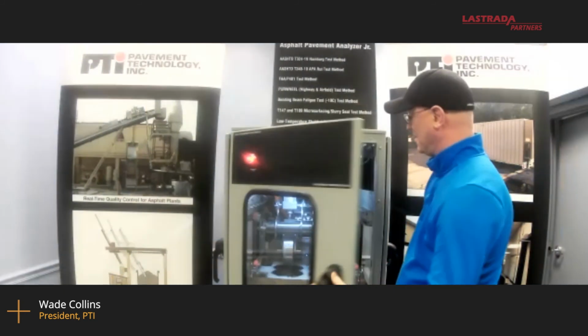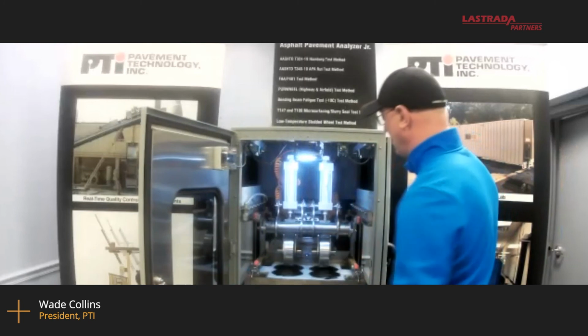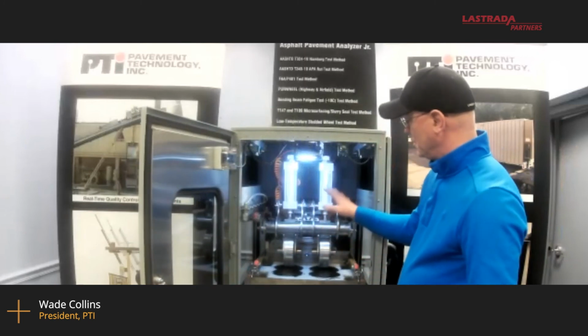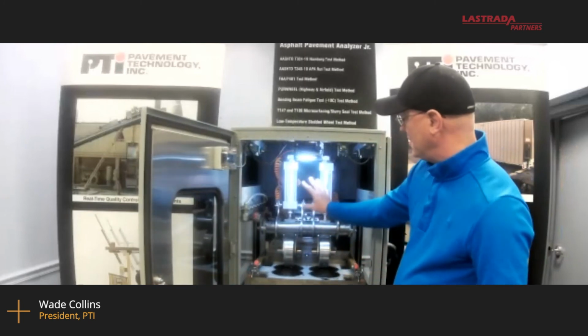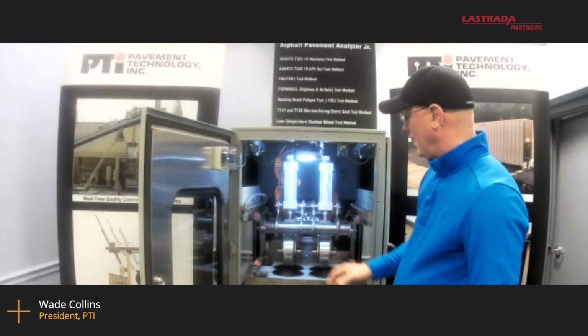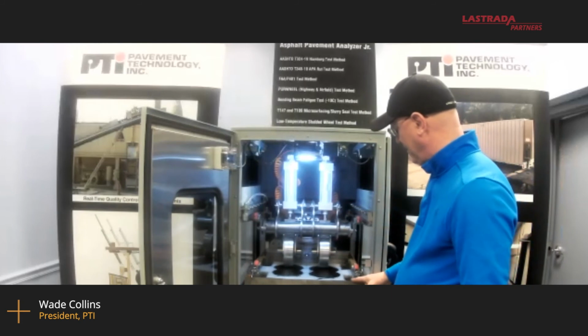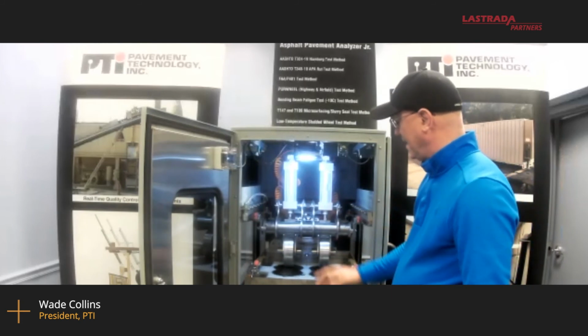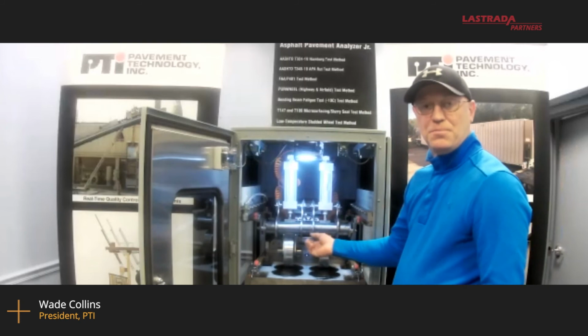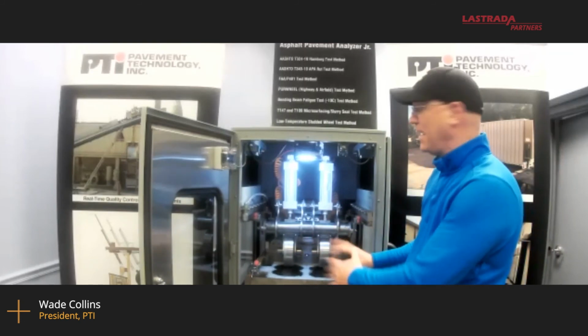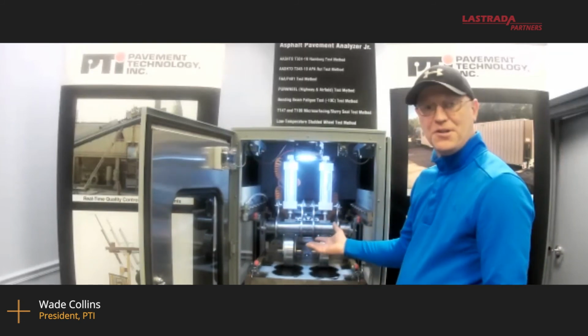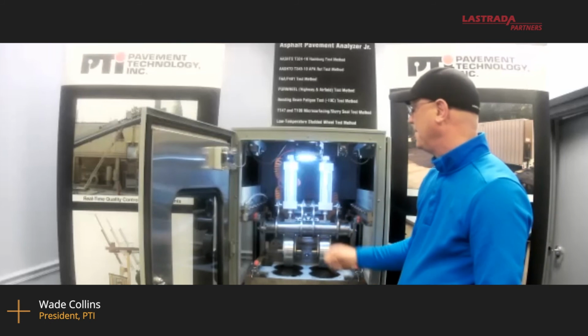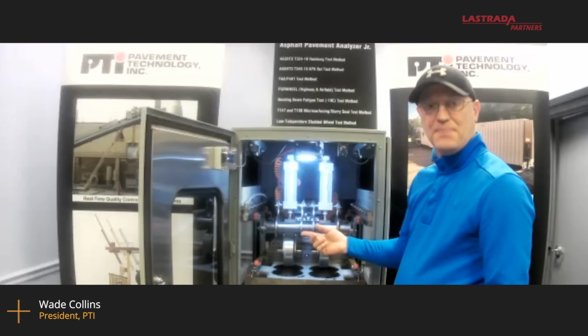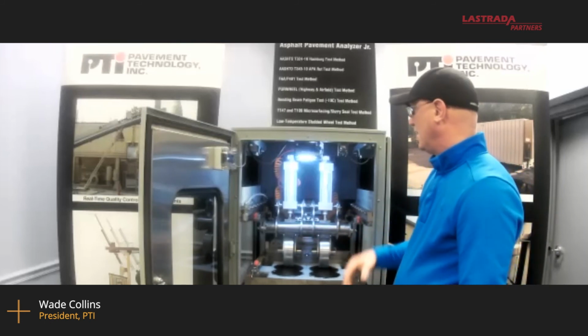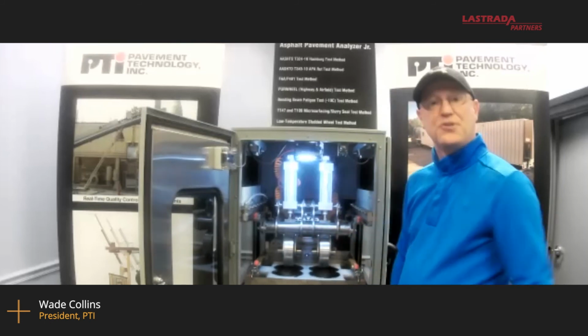If you wanted to put samples in the machine, you would simply open the front door. The wheels come up and the carriage goes to the very back of the machine. You have a gate right here. Let this gate down, and then put your samples in. Close the gate back up, turn on your water pump, and it floods the chamber like you see here. It continuously percolates and maintains the temperature of the water. You run through your calibrations and then start your test.